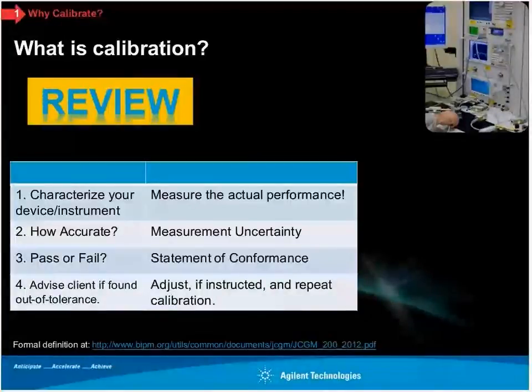So number one, you want to characterize a device or instrument, and you do that by making actual measurements. Well, as soon as you make a measurement, the next thing you want to know is how accurate was that measurement. And in the metrology world, we use the term measurement uncertainty. So that's a standard deviation representation of all of the sources of error combined in an industry standard fashion. Well, once you have a measurement and you know what the statistical measurement uncertainty was, you're then in a position to say, did that measurement pass or fail the warranted specification? And in the metrology world, we call that a statement of conformance.